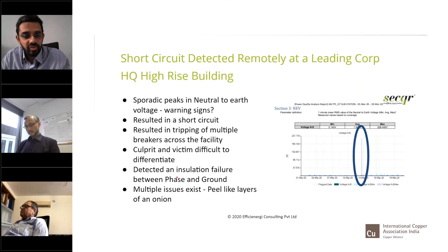One more is a case of a very leading corporate headquarters, I won't name the brand, of a high-rise building where we could spot a short circuit remotely by doing this monitoring. You see over here the neutral to ground voltage going to almost 230 volts in the 2 to 3 weeks that we did the monitoring. Again, it was a detection of an insulation failure between phase and ground, which we were able to detect and help the facility take corrective action much faster. So these are some of the cases of remote power quality monitoring helping you.